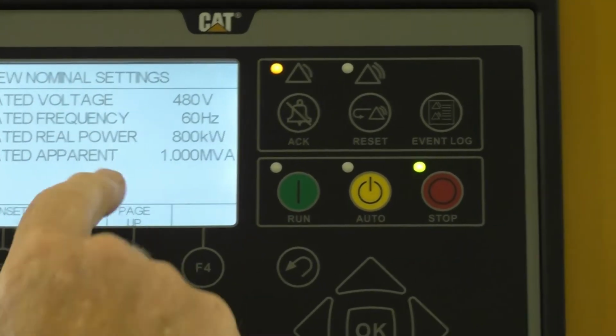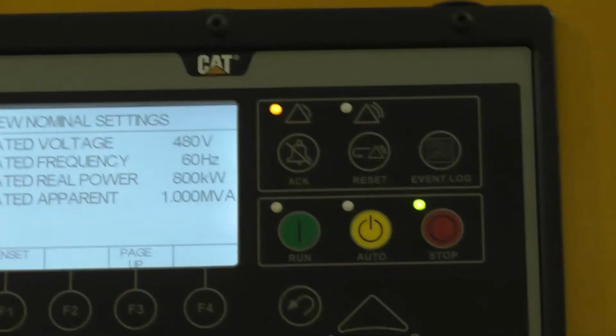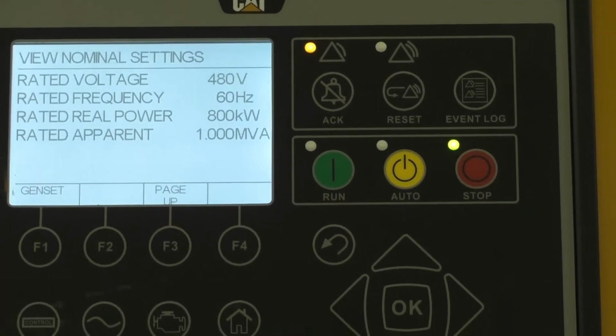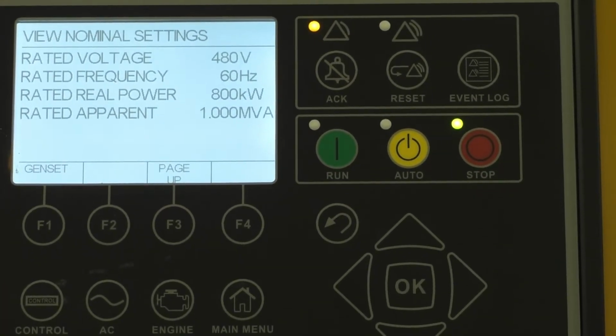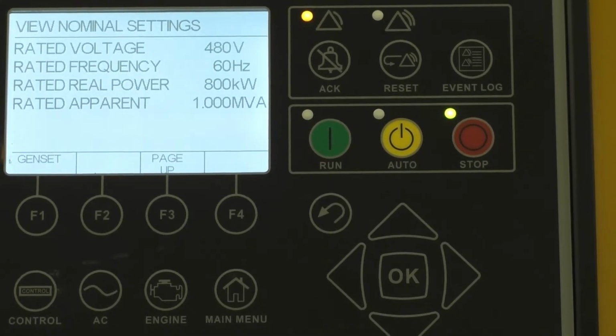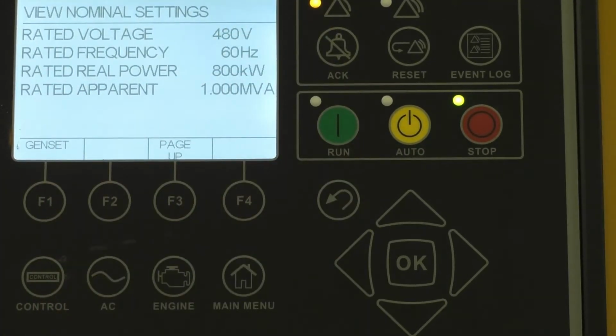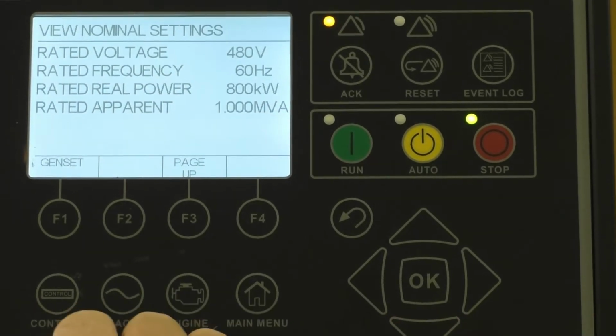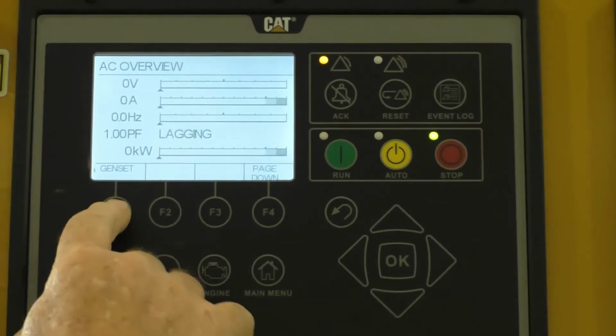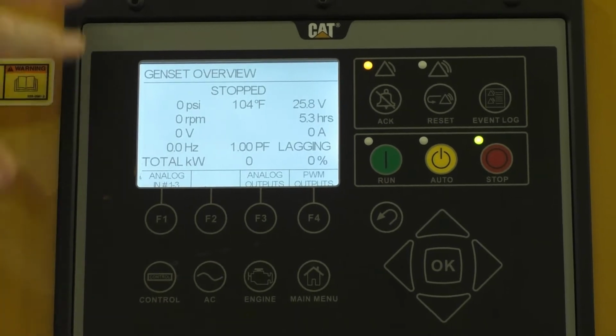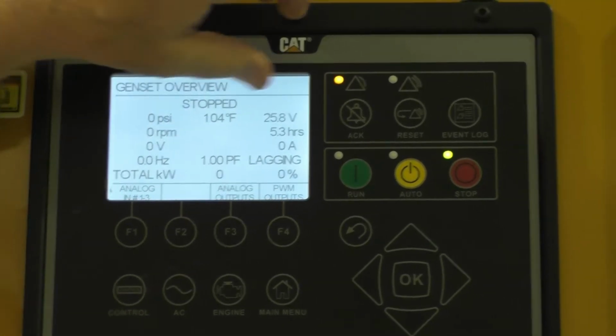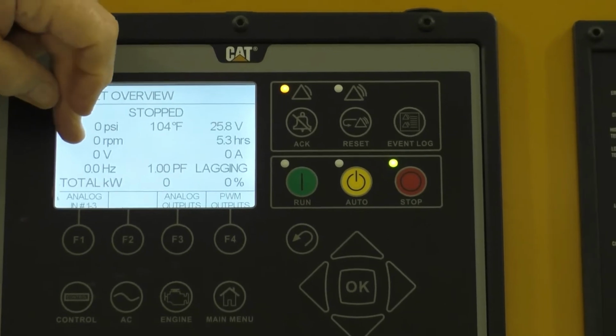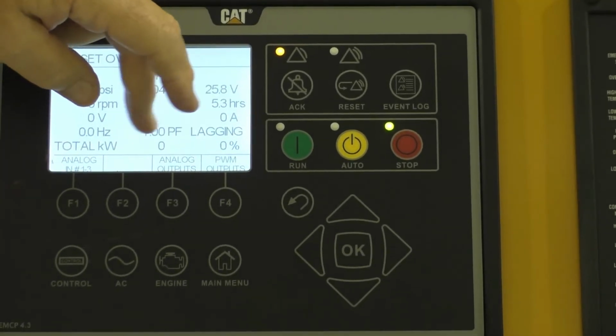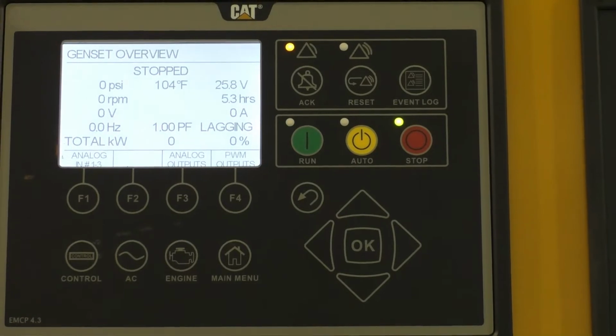The rating on the generator is kind of funny. It says 800 kW and 1000 kVA. kW is volts times amps times 1.732 times 0.8 equals kW. Well, kVA, they don't do the 0.8, so it's a higher number. It actually comes out to about 20% more. So anyway, you can also go here, and that's my favorite screen because it's got everything you need on it. It's got all the engine information on the top half, and the bottom it'll have voltage, amperage, power factor, kW, and percent of load, all in one screen. So the way to remember it is you just hit that button, and then it gives you all.